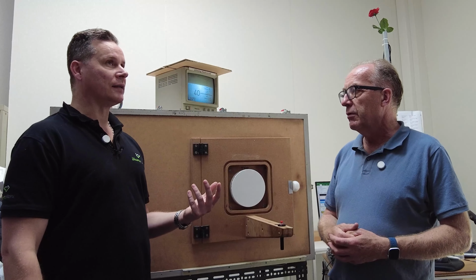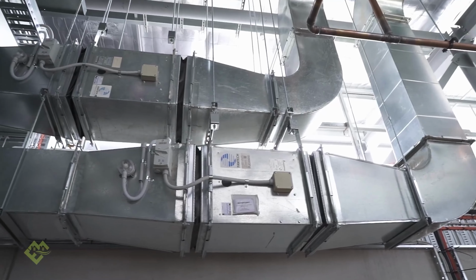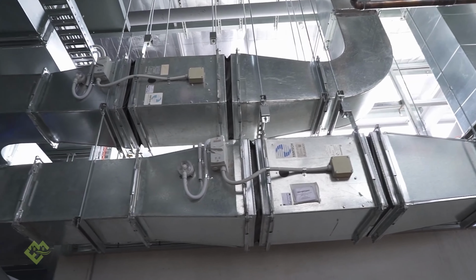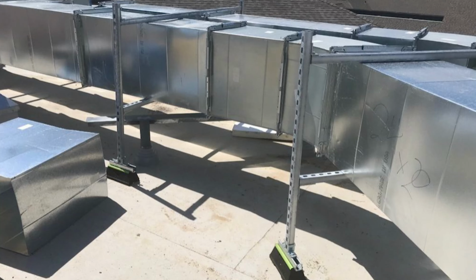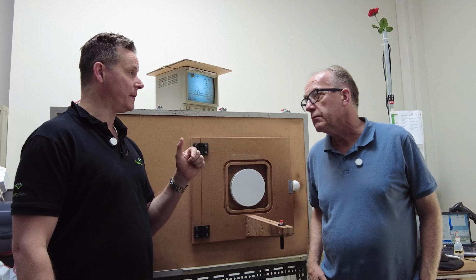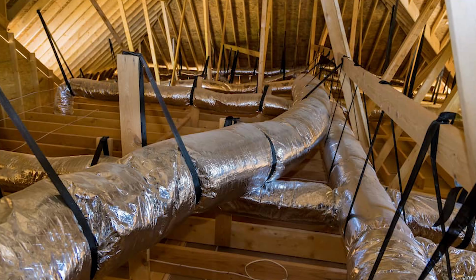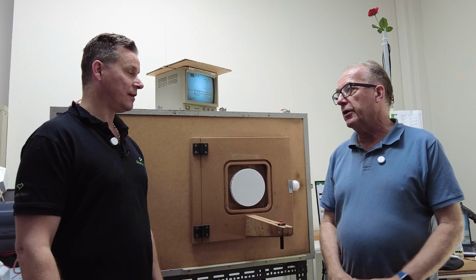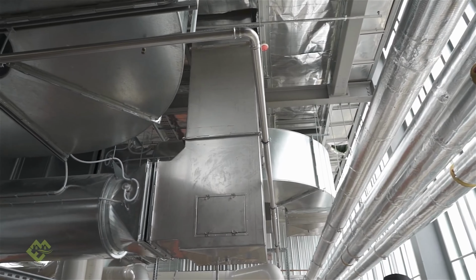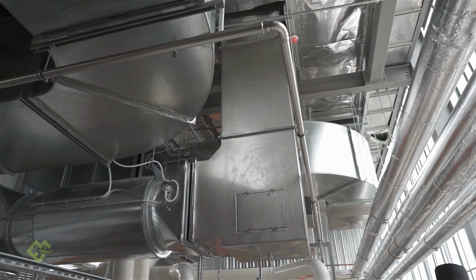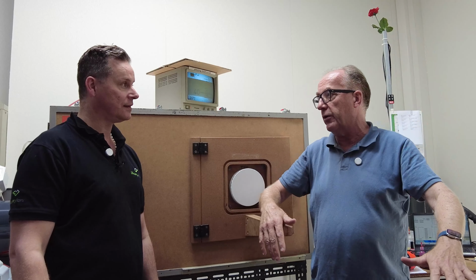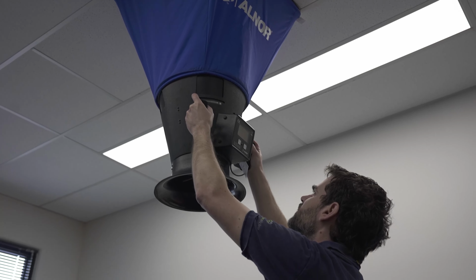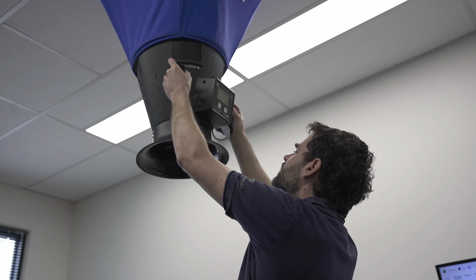Because depending on the runs, you will get different velocity of air coming from ducts or duct openings that are closer to the air handlers too, right? So the way the air comes out of an opening can vary depending on where it is in the duct run, and it can also vary because just behind the grill is a vent. If you have a vent, the air accelerates in a different way, and it doesn't come out like this. But on this side of the grill, the velocity will be higher than on this side of the grill. And if you have a standard passive flow hood, we will explain that later, then it doesn't understand the velocity pattern, and it makes a measuring error.